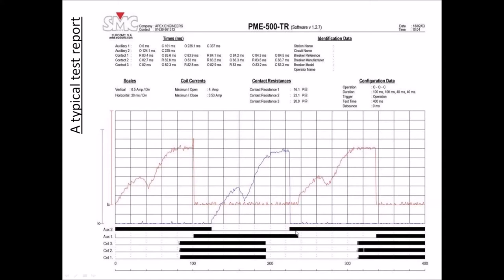These are the auxiliary contacts, shown on a different grid. In the upper section of the graphic you get the coil current — the closing coil activity and the current going across the closing coil during the close command, then the open coil, and then again the closing coil. In the same report you can also see a contact resistance measurement for the three phases.